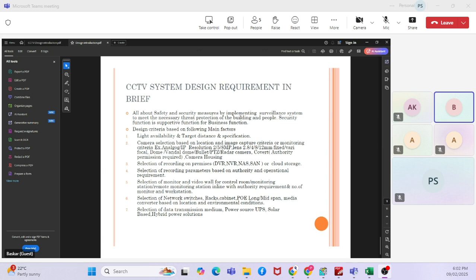If the local regulation is asking for 20 percent, but the client is asking for 30 percent spare, or if the local regulation is asking for 30 minutes and the client is asking for 1 hour battery backup, you have to choose based on the higher requirement always. If you choose the lower requirement, when we win the project, you will be losing from your margin.